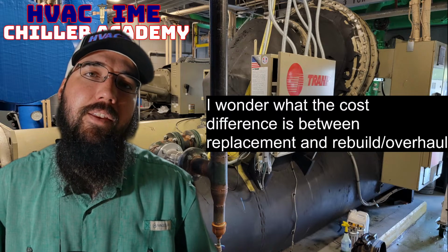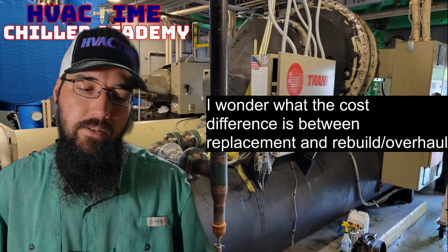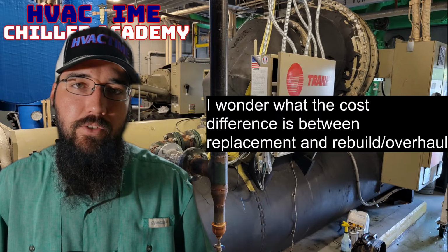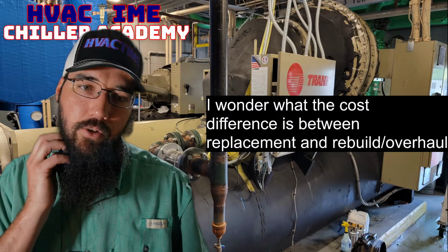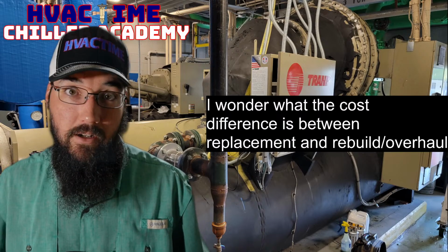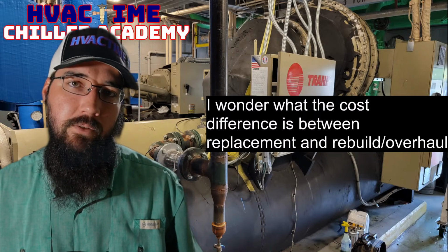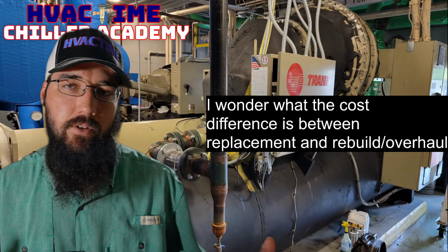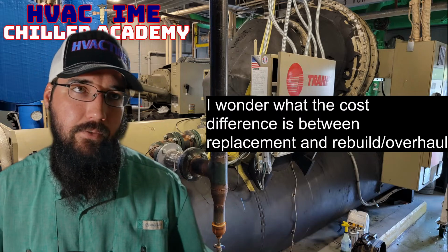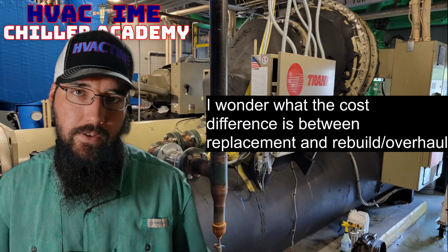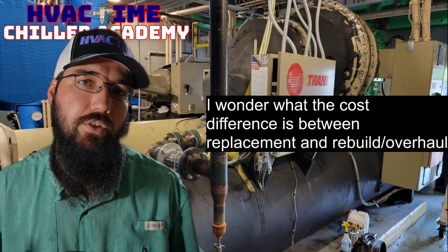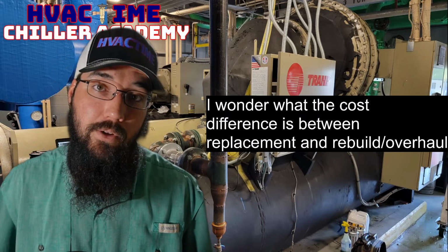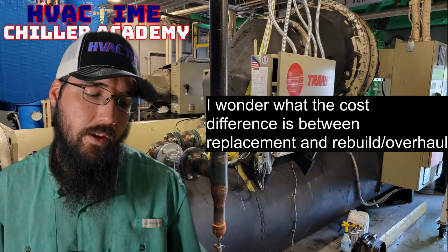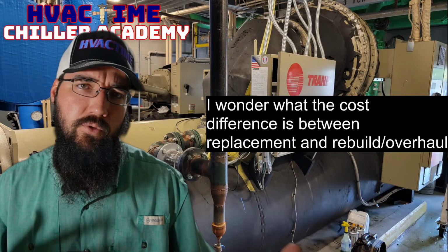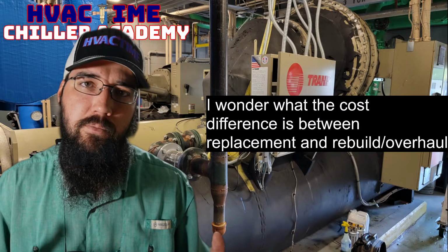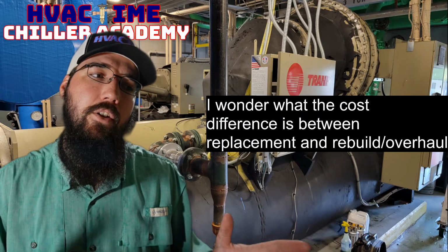This is really circumstantial, heavily. A lot goes into making this decision - I mean, a lot. So the scale of the machine would be one thing. Some of these chillers, depending on the scale and size, are typically hundreds of thousands at the smaller scales, and then they scale into the millions depending on the size of your equipment. That's also true for the overhaul cost. Your smaller machines are easier to overhaul, and they're going to cost less.